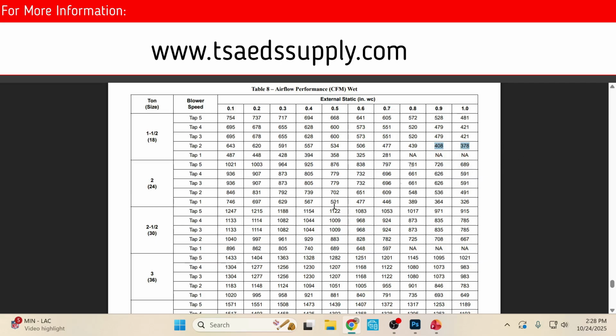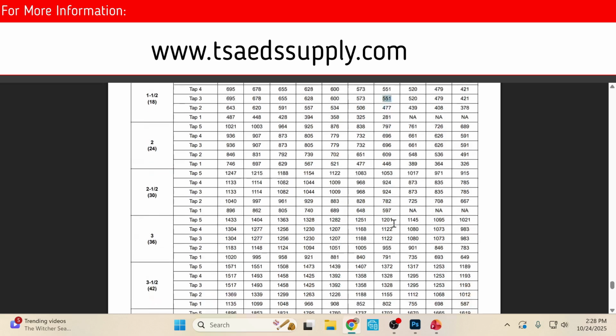So how do you get that? And for those people that are listening that can't see this, you can go to the YouTube page and actually see what we're talking about, and there'll be a link on the website for that. You don't just move the speed tap on the motor up and it automatically does this. You have to read these numbers in your duct that you have, and then you read what is there, and then you adjust the speed tap to confirm that the speed tap, along with this, delivers this. And once that triangle of those 3 numbers is working, you'll have confirmed you have that amount of CFM.